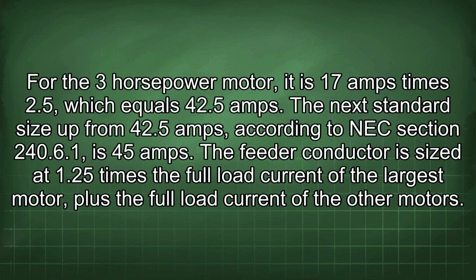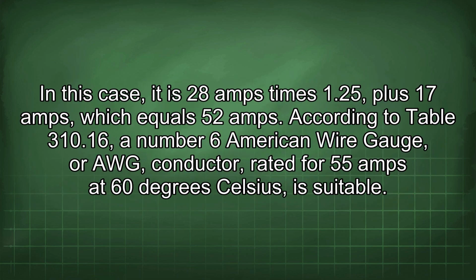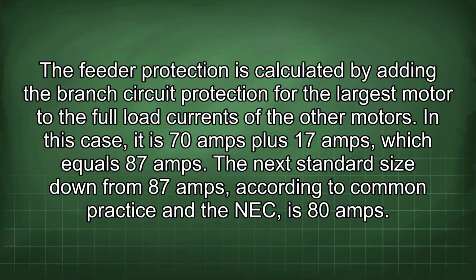The feeder conductor is sized at 1.25 times the full load current of the largest motor plus the full load current of the other motors. In this case, it is 28 amps times 1.25 plus 17 amps, which equals 52 amps. According to Table 310.16, a number 6 American wire gauge, or AWG, conductor rated for 55 amps at 60 degrees Celsius is suitable. The feeder protection is calculated by adding the branch circuit protection for the largest motor to the full load currents of the other motors. In this case, it is 70 amps plus 17 amps, which equals 87 amps.